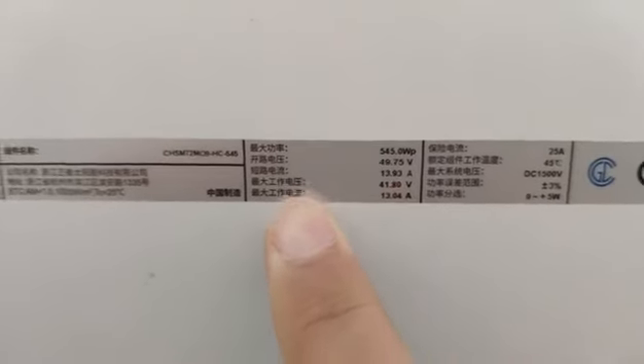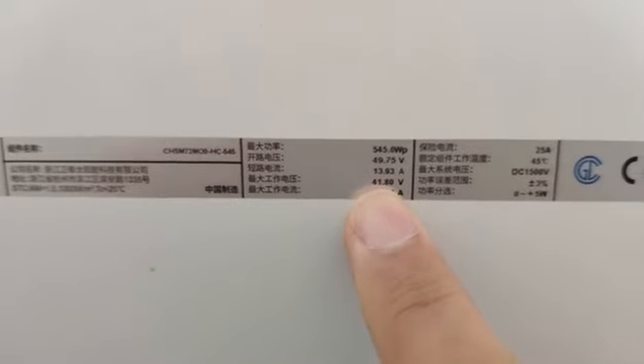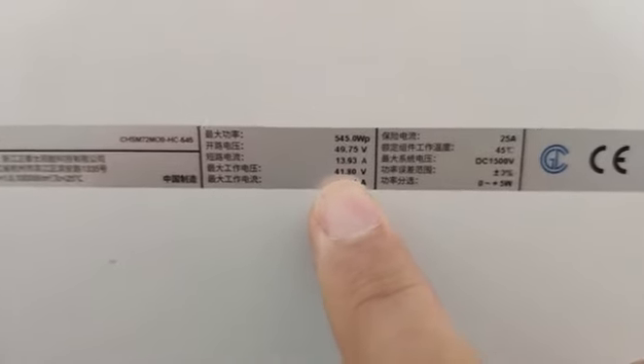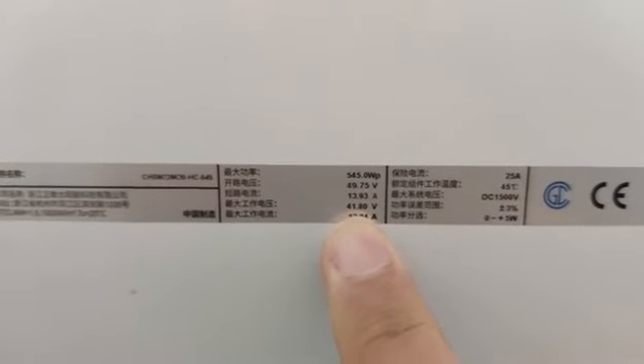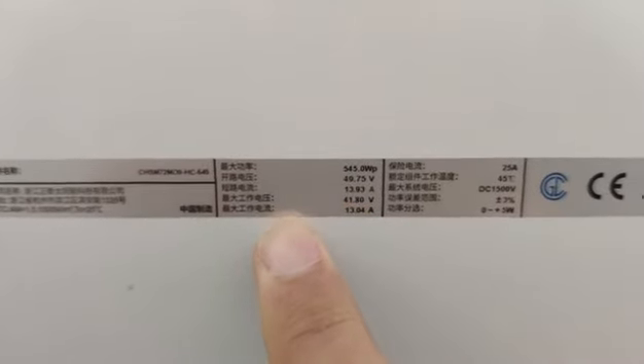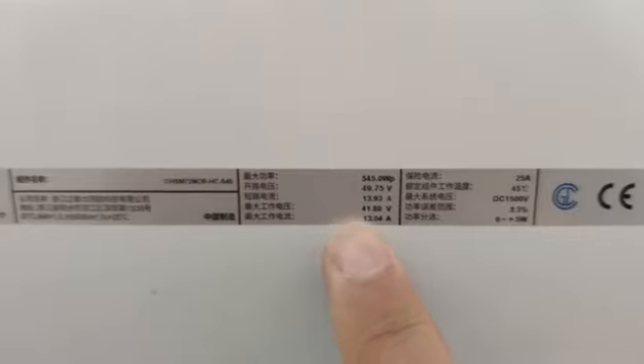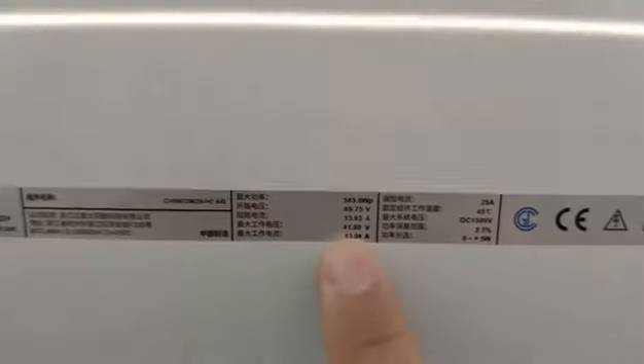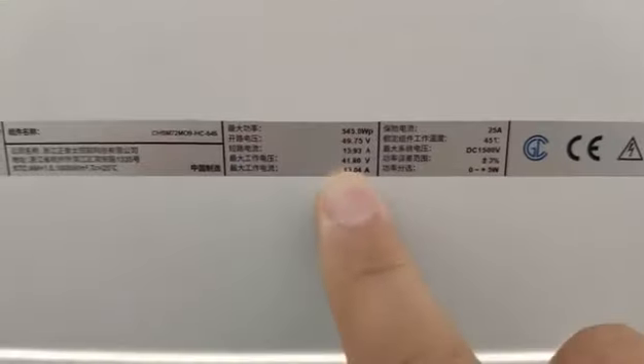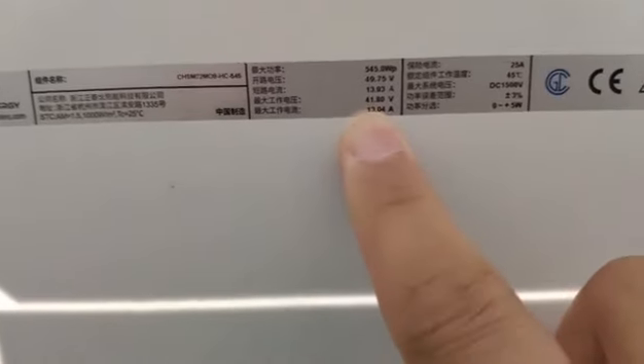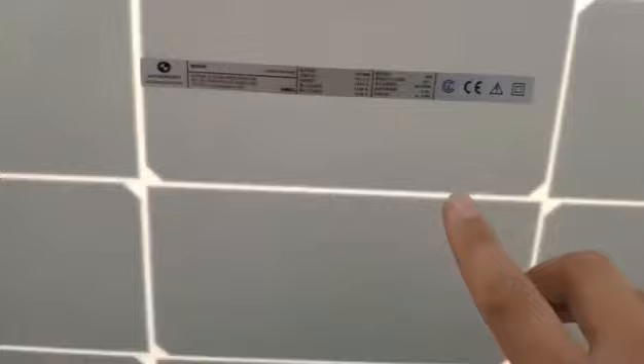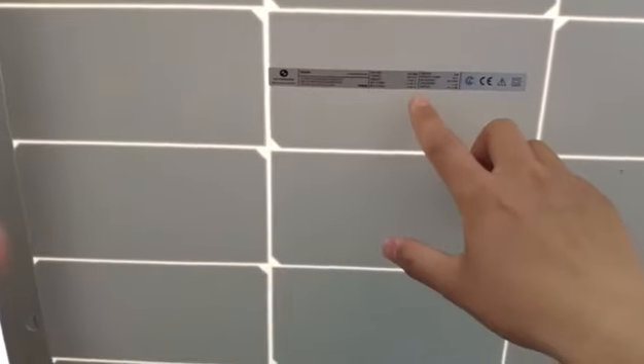Let me tell you why there was a safe current just now, and about the maximum system voltage. This system's boards can be assembled and connected in series, but the final voltage you reach must not be higher than 1500 volts.